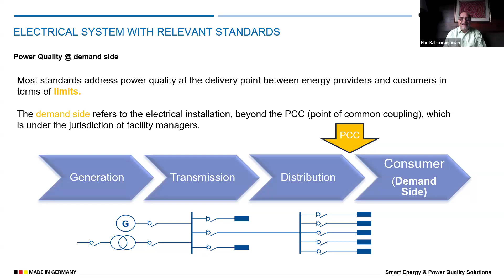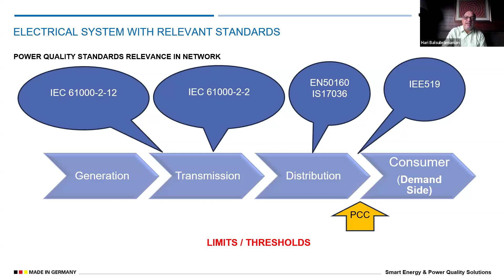So what standards do we have relevant to the network? You have 61000-2-12 for transmission, EN50160 and IS17036 for distribution systems, and IEEE 519 for consumers, which clearly says voltage is the responsibility of the distribution companies and current harmonics is the responsibility of the consumers. All these give limits for individual harmonics, TDD, THD, everything specified, and we have to work within the thresholds given in the standards.